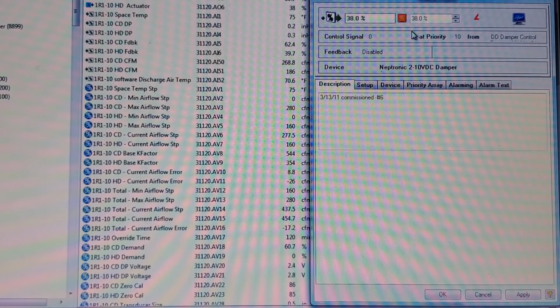Usually you don't have to calibrate at 2 points. Typically you only calibrate at the max, and then you'll double check it at the min just to make sure your calibration holds, and generally it will. So once you've logged into the BAS, you're going to drive the terminal unit to its max flow set point.